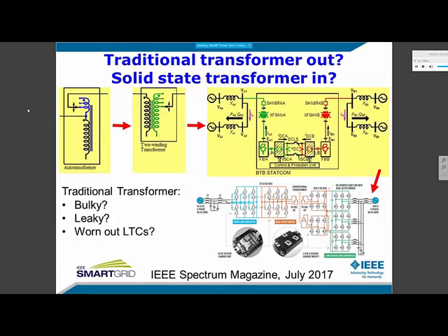Now, these transformers also were acting as filters, not just isolation. So because these transformers are gone, now we need two sets of filters at both ends. And notice that this transformer has 9 windings compared to 6 windings in the old transformer.